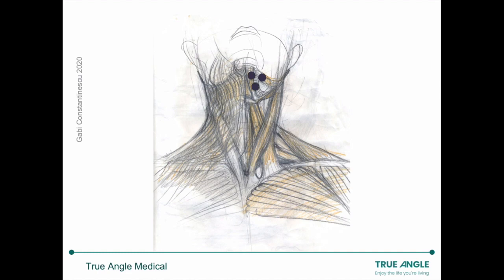That ground sensor can really go anywhere where there's a bony prominence—your forehead, your elbow—but in the case that I've shown you, the three sensors are connected together by that sticker. So the ground will have to go on the mandible.